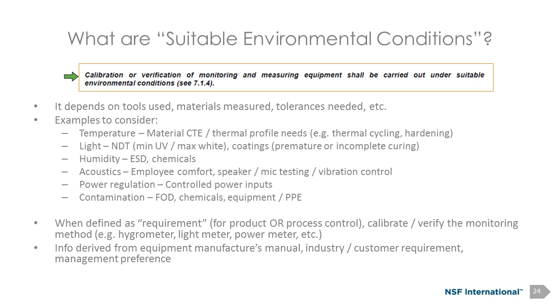Within 7.1.5, it's speaking more of the calibration or the verification lab, if you will, where that effort's being done. And while a mechanical tool may not necessarily be impacted by humidity or light, some other tools absolutely could be. When we think about our NDT processes, the UV light or the white light environment is going to be directly impactful to the effectiveness of our NDT operations, non-destructive testing operations. So as I'm calibrating those types of instruments, or I'm verifying those types of instruments, we need to be cautious of the ambient light.